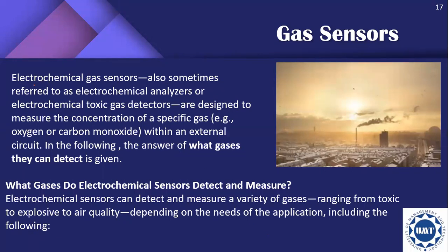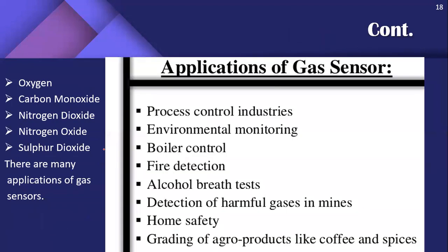Gas sensors are also referred to as electrochemical analyzers or electrochemical toxic gas detectors, designed to measure the concentrations of specific gases such as oxygen or carbon monoxide within an external circuit. Electrochemical sensors can detect and measure a variety of gases including oxygen, carbon monoxide, nitrogen dioxide, and sulfur dioxide.